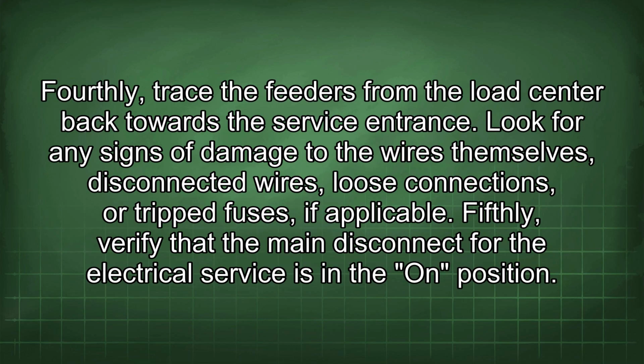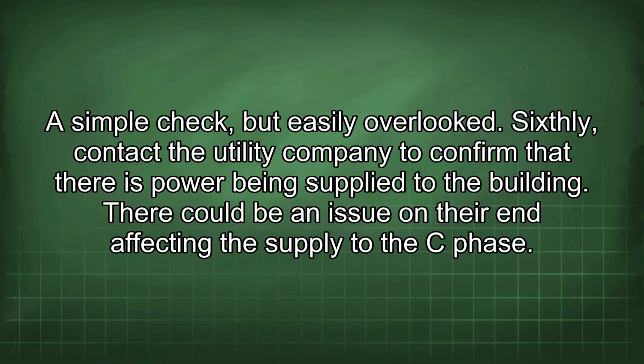Fourthly, trace the feeders from the load center back towards the service entrance. Look for any signs of damage to the wires themselves, disconnected wires, loose connections, or tripped fuses, if applicable. Fifthly, verify that the main disconnect for the electrical service is in the on position. A simple check, but easily overlooked. Sixthly, contact the utility company to confirm that there is power being supplied to the building. There could be an issue on their end affecting the supply to the C phase.